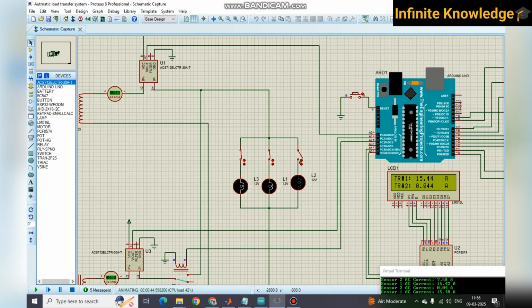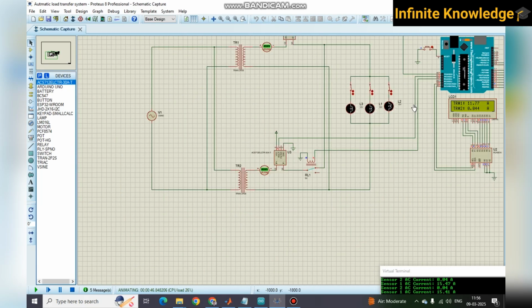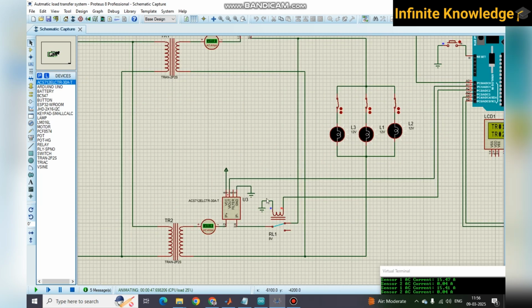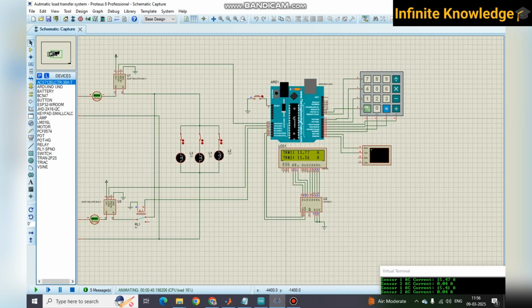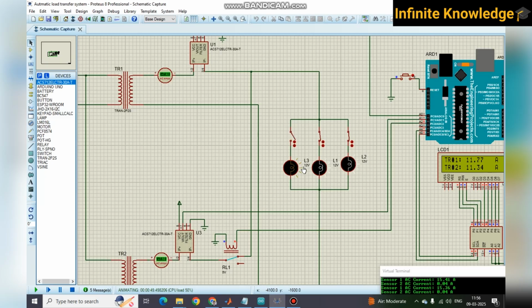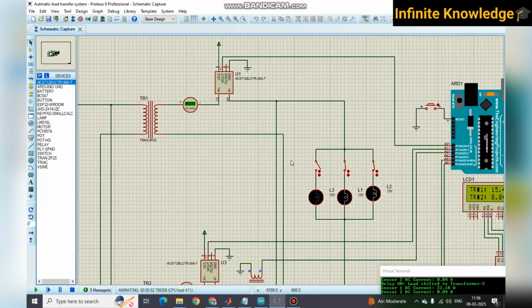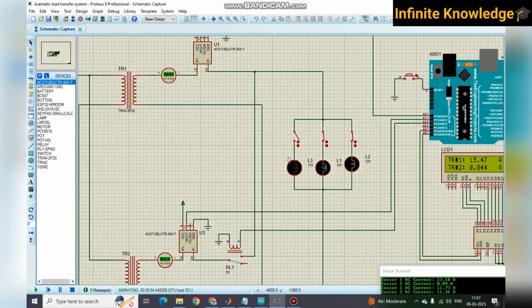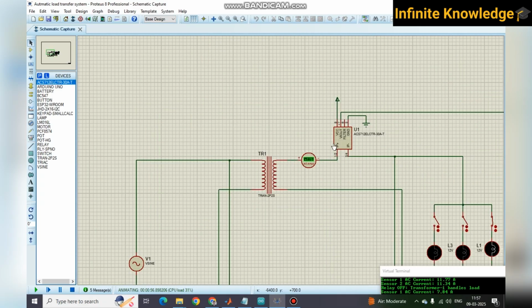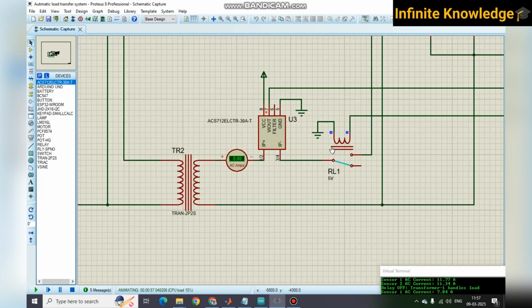Again, if I switch on another load, both transformers come into the picture and share the load. Right now both are sharing the load. Now if I isolate one of the lamps, both are taking a lower ampere, less than 10 ampere. At the same time, TR2 is isolated, and there is a slight delay to avoid unnecessary start and stop. So again TR2 is isolated and only TR1 remains, and if I reduce the load again, only 7 ampere is taken by this one, and there is no ampere on this one because it is isolated.